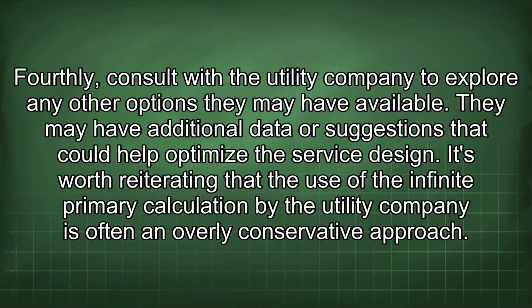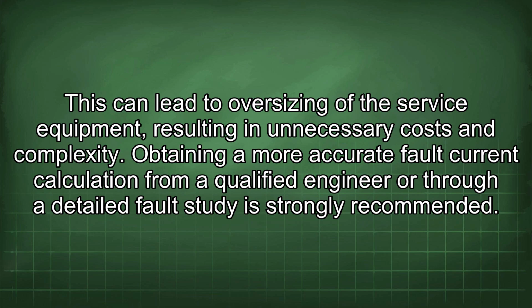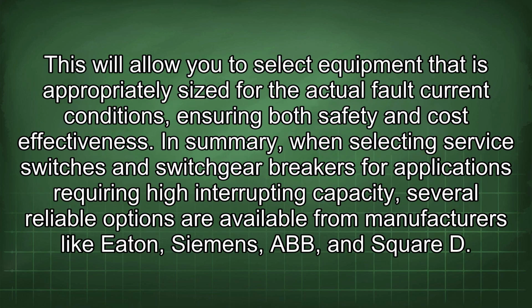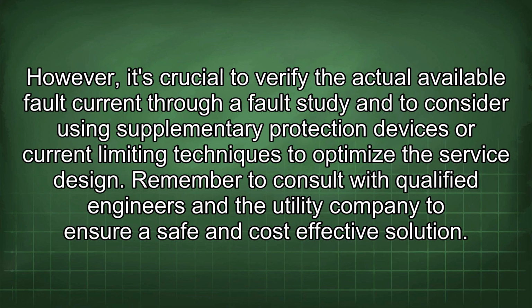It's worth reiterating that the use of the infinite primary calculation by the utility company is often an overly conservative approach. This can lead to oversizing of the service equipment, resulting in unnecessary costs and complexity. Obtaining a more accurate fault current calculation from a qualified engineer or through a detailed fault study is strongly recommended. This will allow you to select equipment that is appropriately sized for the actual fault current conditions, ensuring both safety and cost-effectiveness. In summary, when selecting service switches and switchgear breakers for applications requiring high interrupting capacity, several reliable options are available from manufacturers like Eaton, Siemens, ABB, and Square D. However, it's crucial to verify the actual available fault current through a fault study and to consider using supplementary protection devices or current limiting techniques to optimize the service design. Remember to consult with qualified engineers and the utility company to ensure a safe and cost-effective solution.